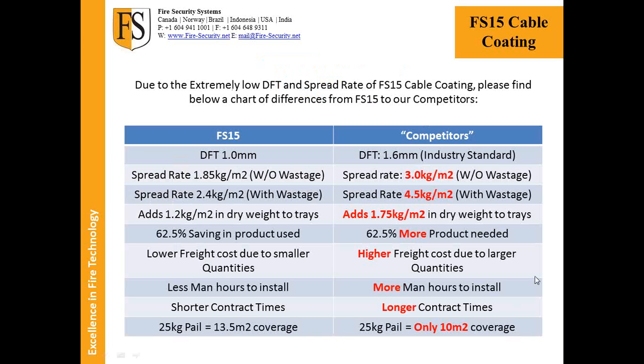So when we come to charts against our competitors and other manufacturers of cable coatings, we find that due to our low DFT and spread rate of FS15, there is a vast difference between us and the industry standards. As you'll see here, the industry standard on average is 1.6 millimeters, and this is for propagation of flame spread under FM approval. Ours, of course, under FM approval is 1.6, but we also have our fire rating approval under IEC, which is 1 millimeter. Therefore, why would we sell a spread of flame coating at 1.6 when we can sell our fire rated coating at 1 millimeter?